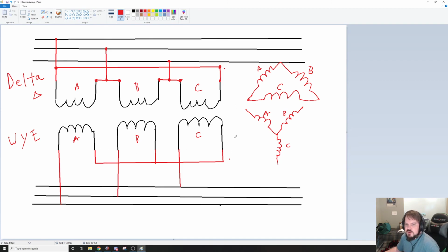A good way to remember that: a Y transformer is going to be like 120/208 or 277/480. So you can see that the bottom number is not half of the upper number, or the upper number isn't twice the bottom number, however you want to say it. Where here, your delta transformer is going to be like 120/240, or you're not going to have a 240/480, but that is another option.